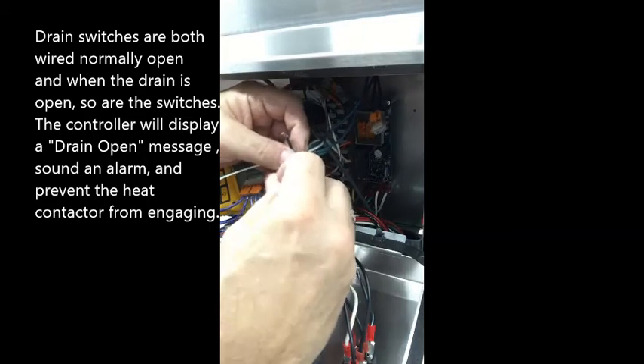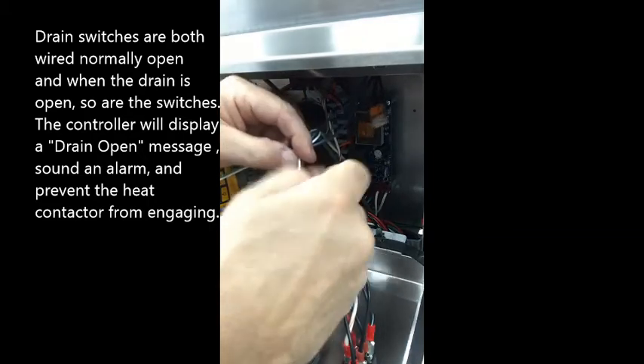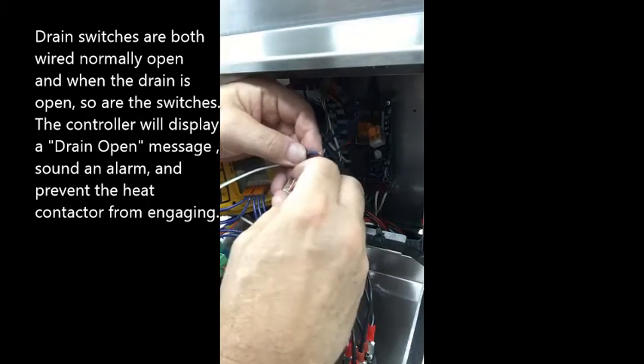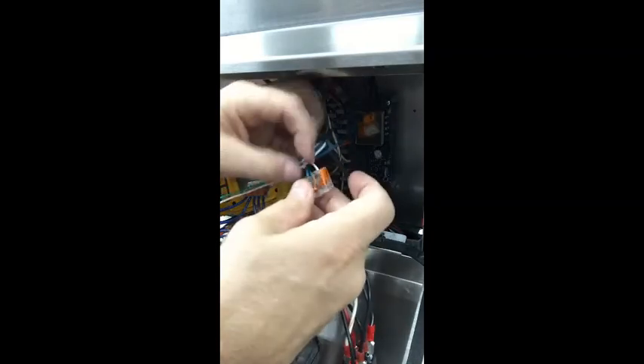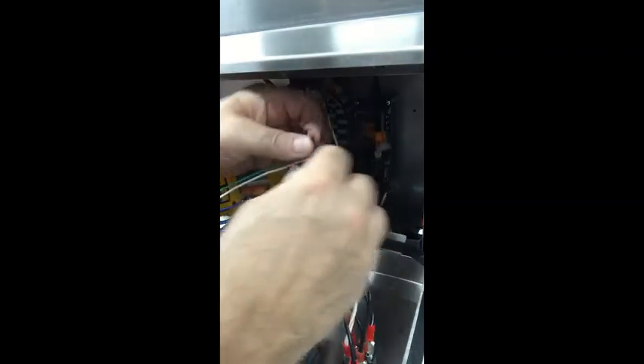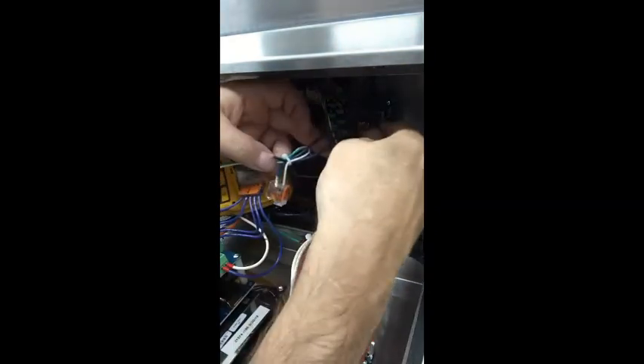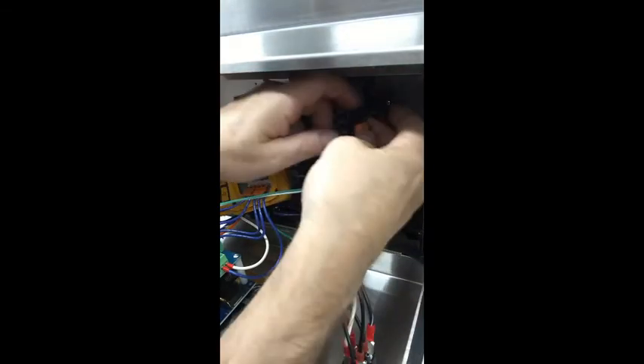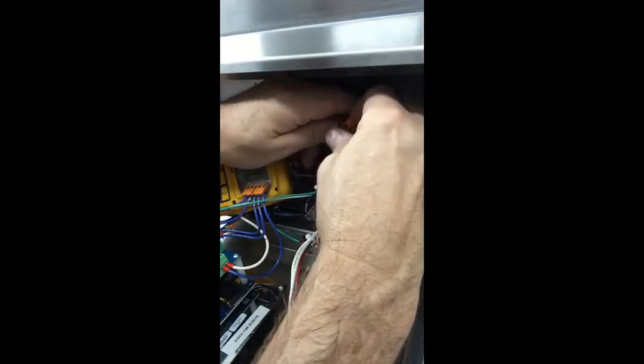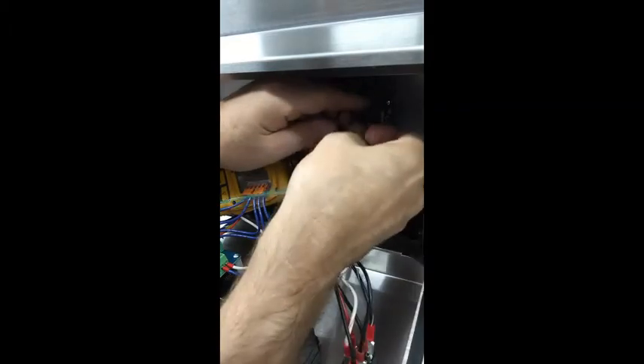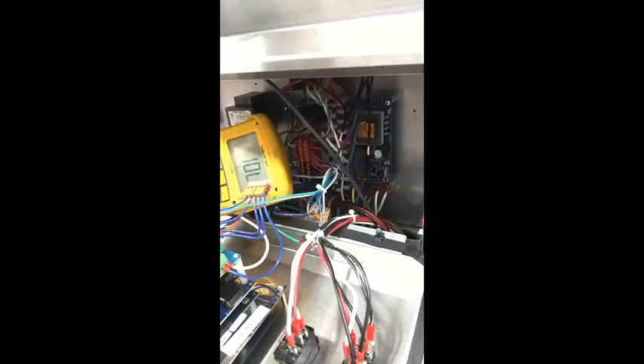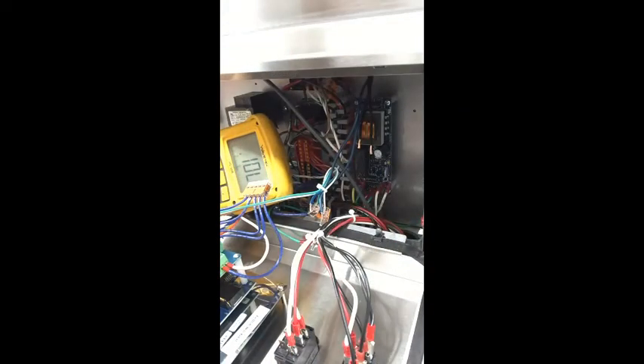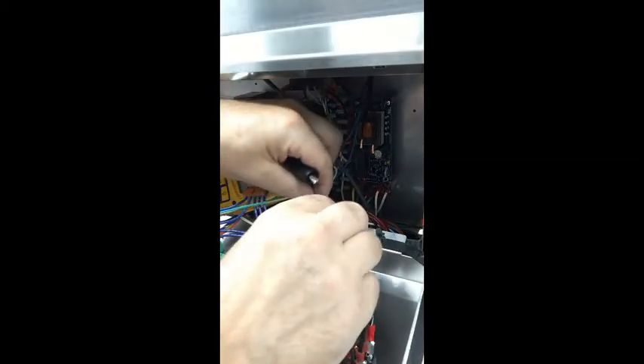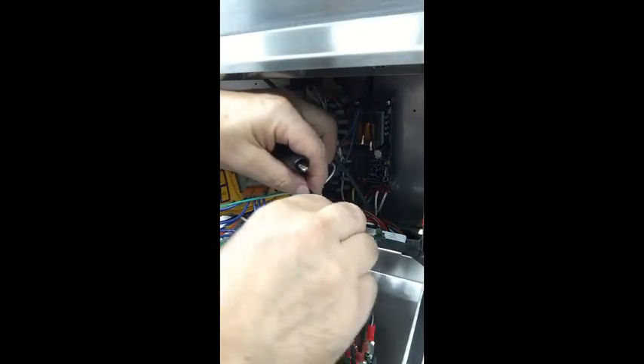So we're going to take the blue wires loose. These little Wago wire nuts, if you just pull down the little clip, the orange clip, it'll release the wire. Now, if you follow them again, they come out and they also go to black, I mentioned before. So we're going to release both of the black. So now we've got the 2 black wires and blue wires loose. So let's go ahead, we're going to clip onto one of these blue wires. We've got the drain closed right now.